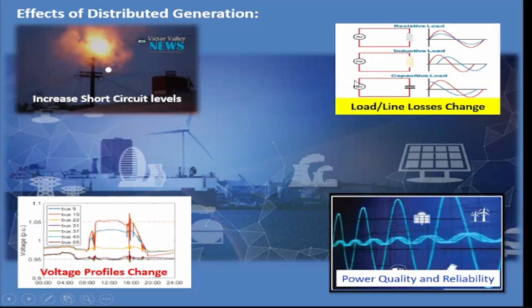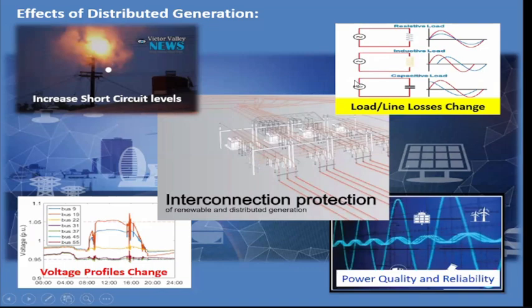On the other hand, under voltage or under frequency if the generation is insufficient. So those impact the power quality. And then, most importantly, network protections may not function properly due to the configuration of interconnection transformers, which will be discussed in detail later. So therefore, interconnection protection for distributed generation and renewable energy is crucial, and will be the focus of our discussion.